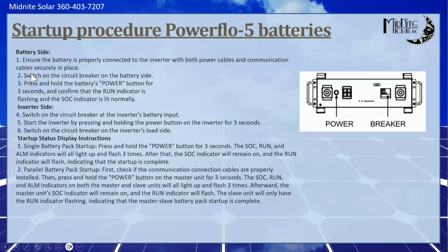How to bring the system online: switch the breaker on the battery on, press and hold the battery's power button until the run light comes on, then switch your inverter on. If you've got an all-in-one, hold the button on the side until it beeps and turns on. If you've got a Rosie, it's already on since it turns on by default when you apply DC power. Then switch on the circuit breakers on the inverter's load side to power your loads, and then the grid, etc. That's the startup sequence.